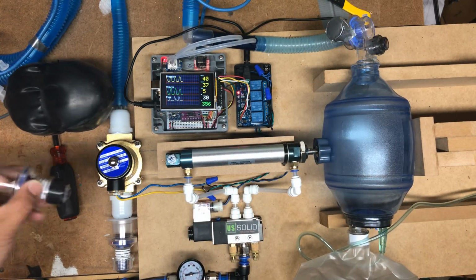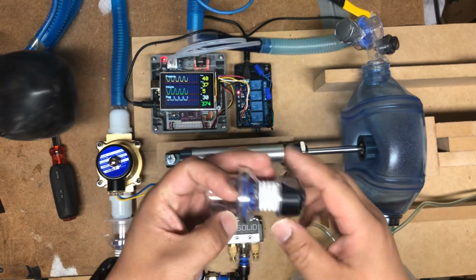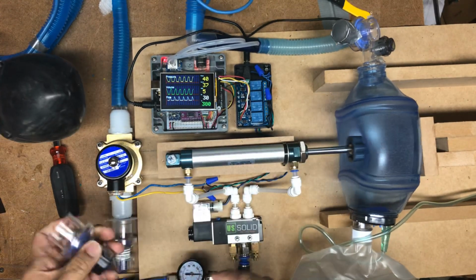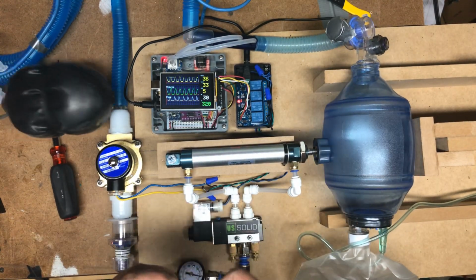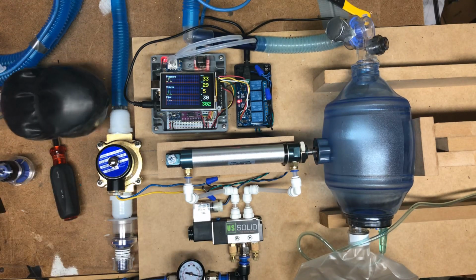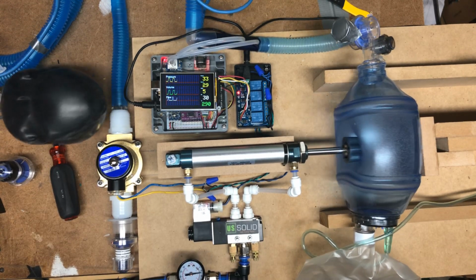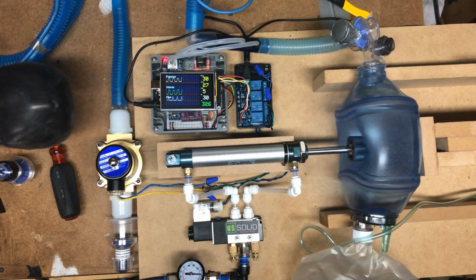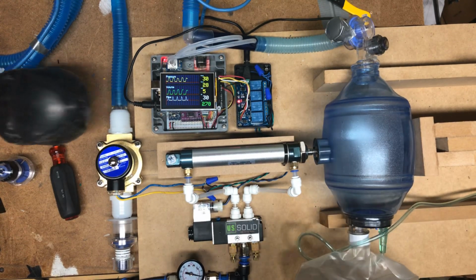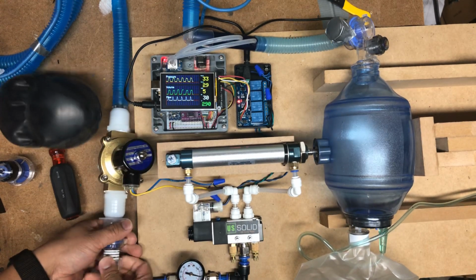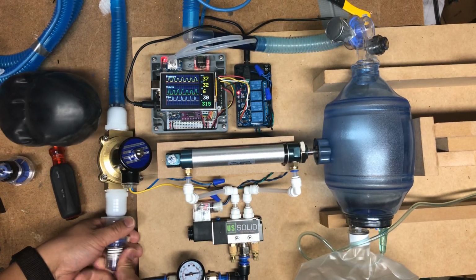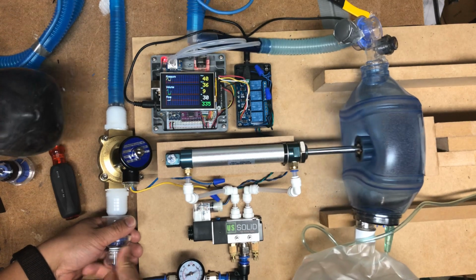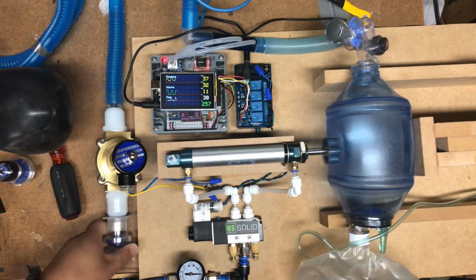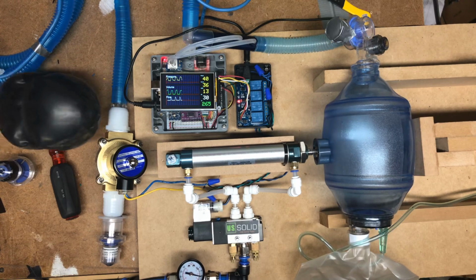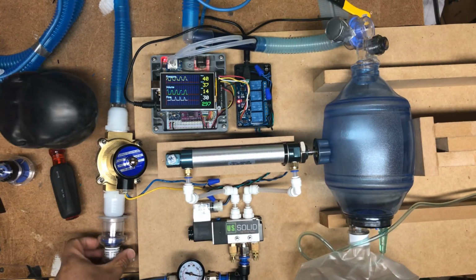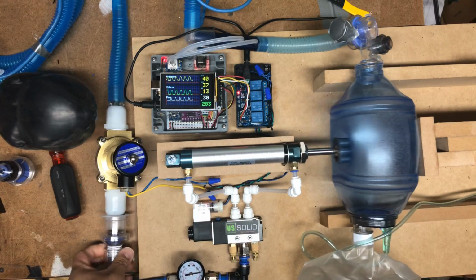We also have a hacked PEEP valve here with a replaced spring to provide you a 40 centimeters H2O adjustable range pop-off valve. We can adjust the PEEP and the PEEP valve here on the exhaust. Let's raise it up a little higher. Turn it back down.